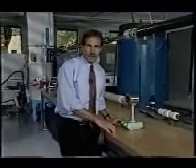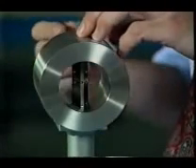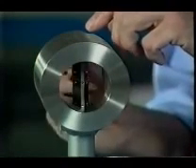and we looked at a vortex shedding flow meter at Omega, which uses this principle. This is an example of a vortex shedding flow meter. The flow causes vortices to be shed off this vortex generator, which you can see here in the tube. The vortex shedding frequency is related to the flow rate, and the shedding of the vortices is picked up by an optical sensor located in the vortex generator.